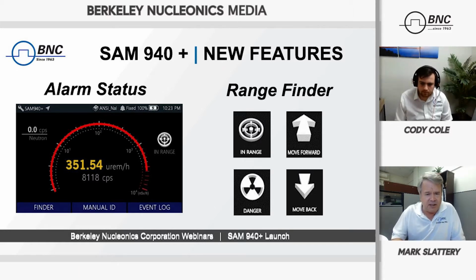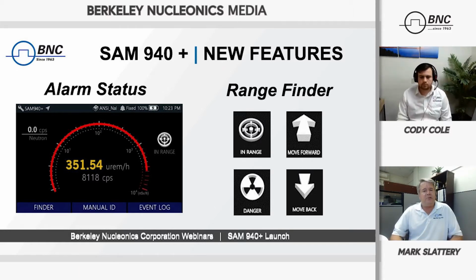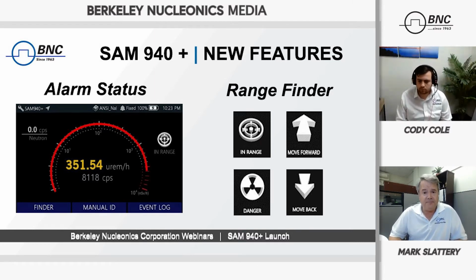So keep getting closer. When you're in a range of about 2,000 to 3,000 counts per second, it should change and tell you that you're in range. My favorite sweet spot is about that 2,000, 3,000, but 5,000, 8,000, those are all good ranges with which to perform your measurements. My feeling is if you can perform the measurement with a lesser amount of counts, why not move back a little bit and perform your measurements there?